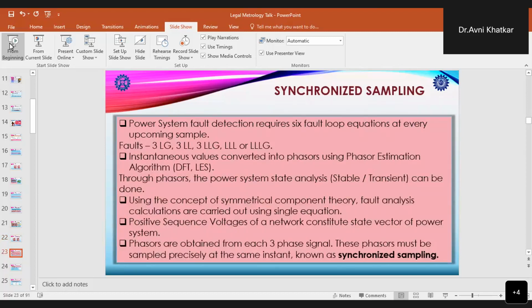So now when we talk about phasor measurement units, synchronized sampling comes into picture. And when we talk about synchronized sampling, we need to have all the samples of the grid. So for the fault detection process, we require at least 6 fault loop equations for all the upcoming samples in the power system to see all the faults which are existing in the power system.